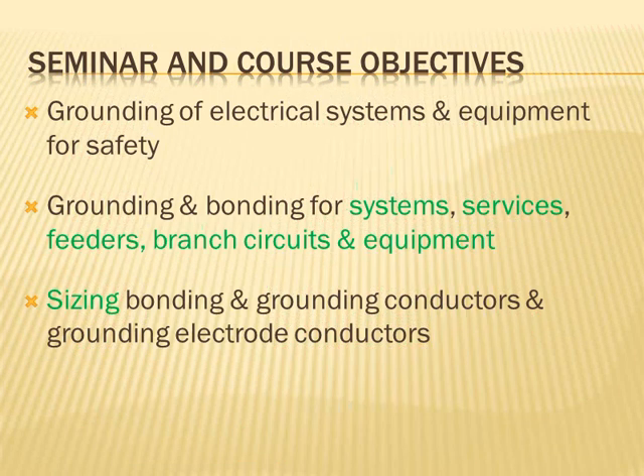So the NEC code book talks about grounding and bonding for systems, services, feeders, branch circuits, and equipment. And I thought this is really interesting, because the first thing you do when it comes to grounding and bonding is the transformer given to you by the utilities. You have a major decision to make: am I running an ungrounded system or a grounded system? That's right here. Then after here, you go to your service. Remember we did all the calculations in service? Regardless if the system is grounded or ungrounded, I have to do certain grounding and bonding in the service. Then you go down to the branch circuits and the feeders and the equipment.